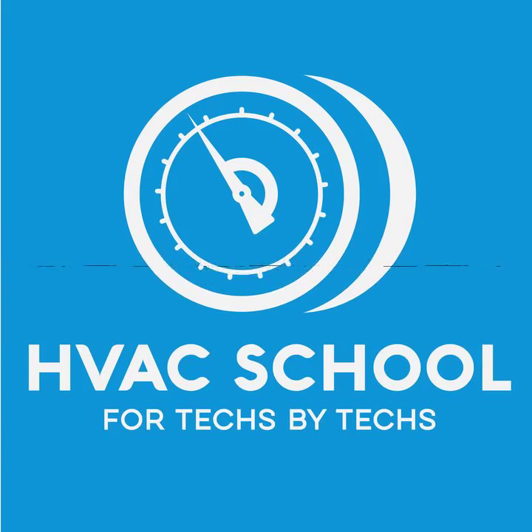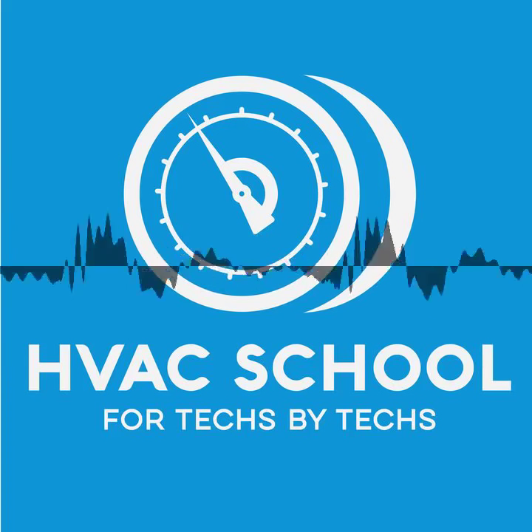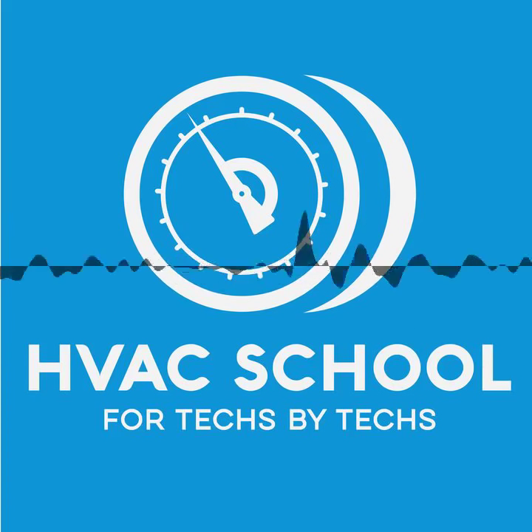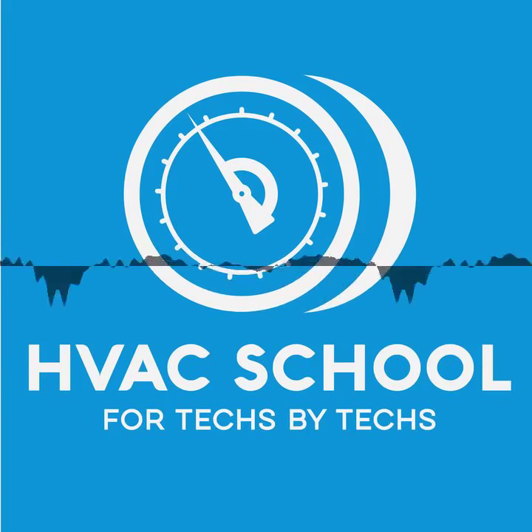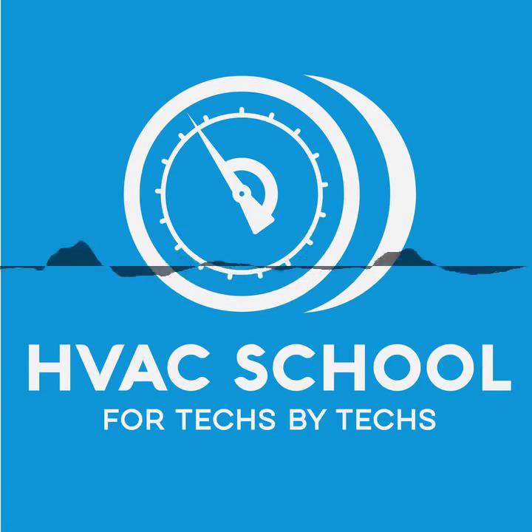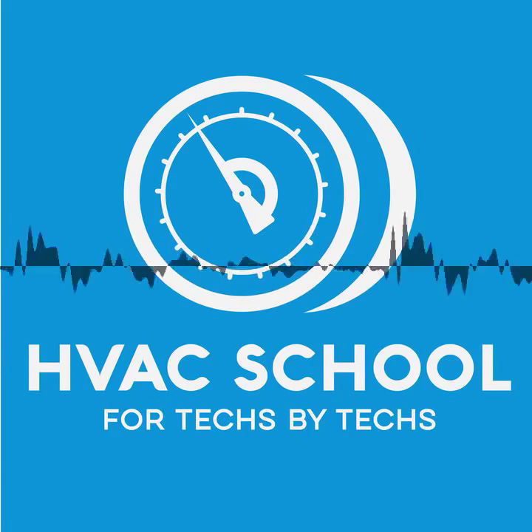And so in some of these more precise manometers, we're not going to talk a lot about blower doors or things like that, but when you get to the more precision devices, those are the ones that you are going to tend to send back for periodic calibration, correct? Absolutely. Yeah, if you're going to maintain that quarter Pascal resolution. And they also have built into them, the ones used for those kinds of products, and again, we're drifting away from combustion, cross-checking valves, little solenoids that will actually shunt the sensor to itself so that it can be zeroed out electronically, digitally. That's how they can maintain that very high resolution and high performance, through an additional mechanical element within the product. That's what makes them expensive, but that's the cost of precision. Got it. And for most of what we're doing with combustion, it's not necessary, with the one exception being if you're trying to measure small pressure differences that exist in that combustion air zone.